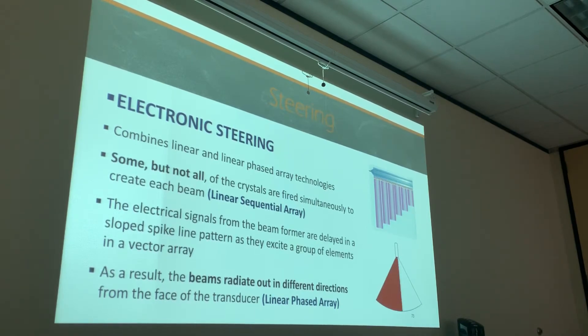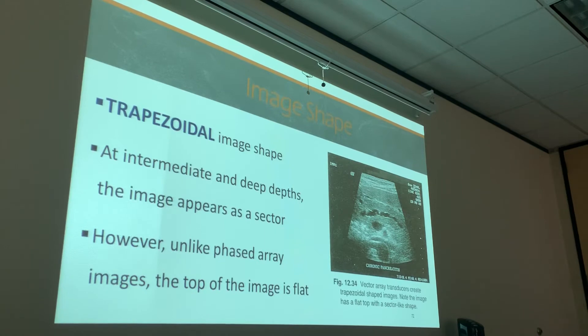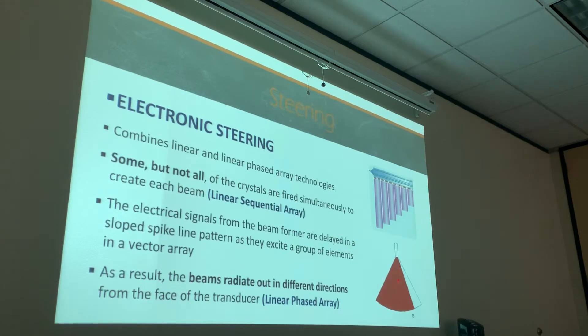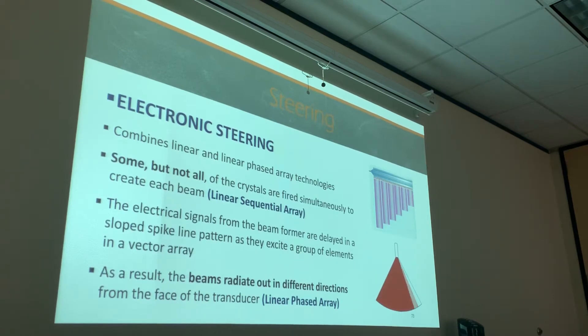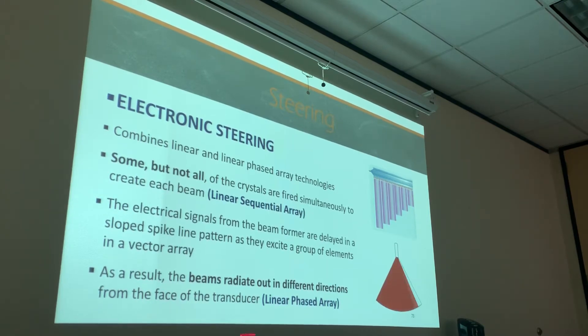How it's like a linear phase array transducer is that the beam radiates out in all different directions like a sector probe. Even though it has a flat top — if it were a linear sequential array, wouldn't this be a rectangular image? But it acts as a linear phased array where the beams actually radiate out, and that's why it creates that somewhat sector-shaped image at intermediate depths. That's how we get that trapezoidal-shaped image.